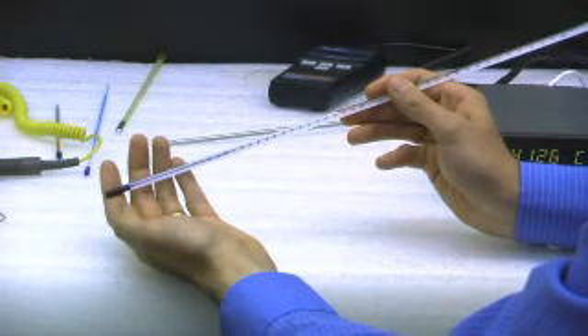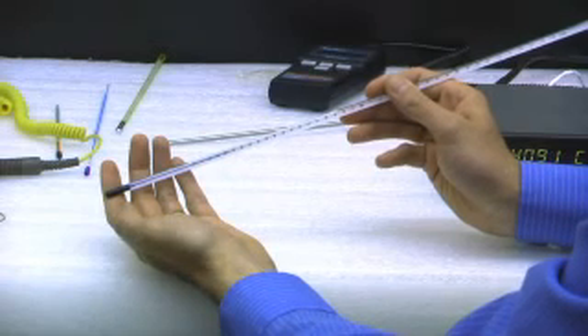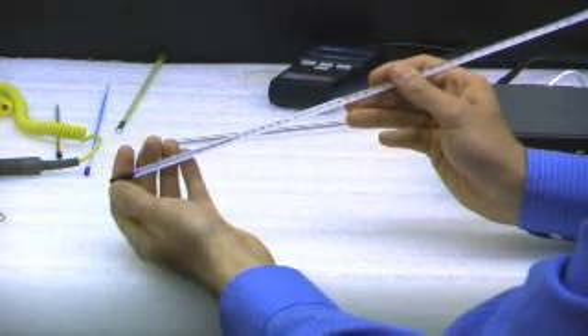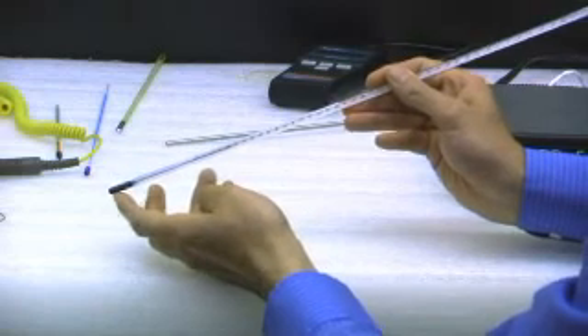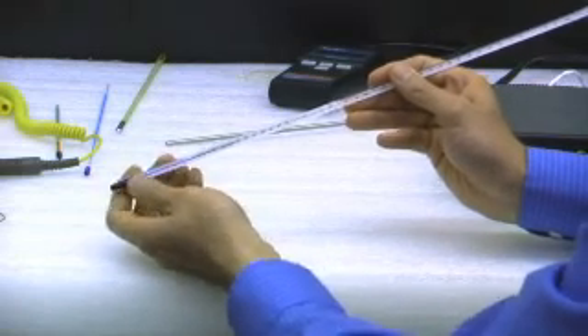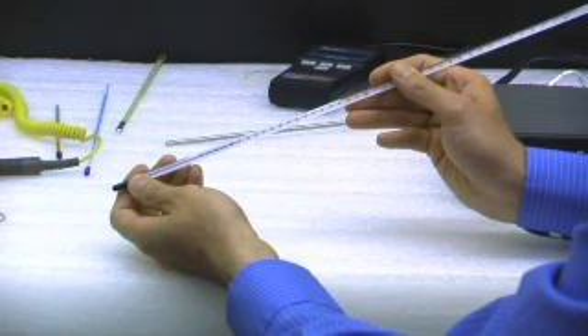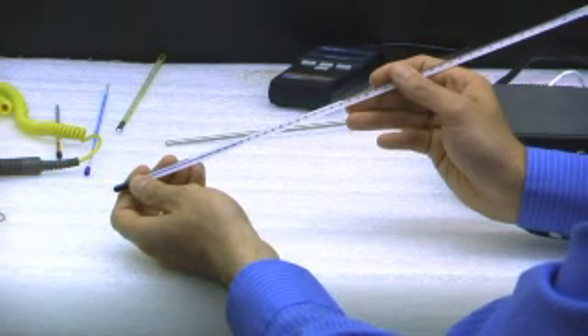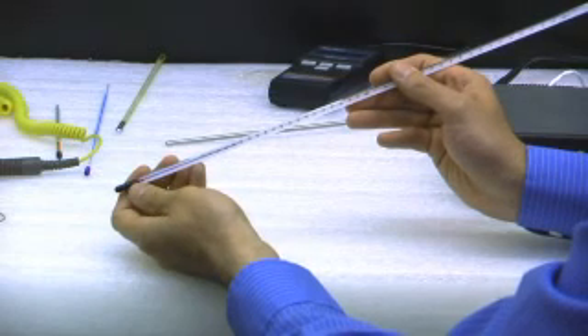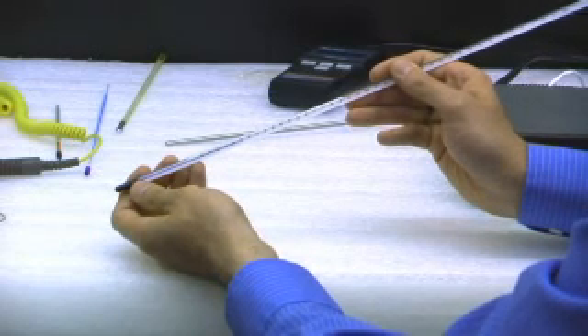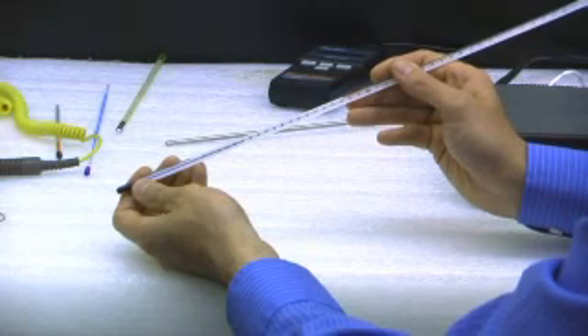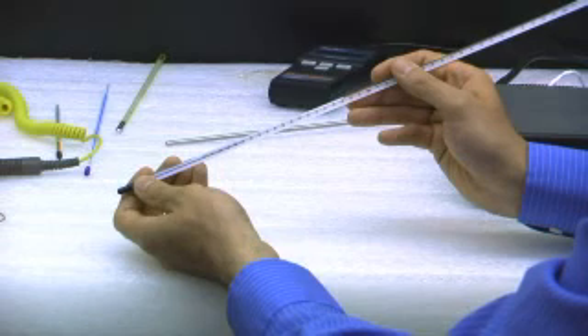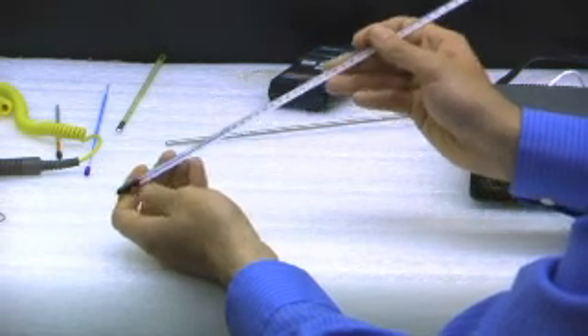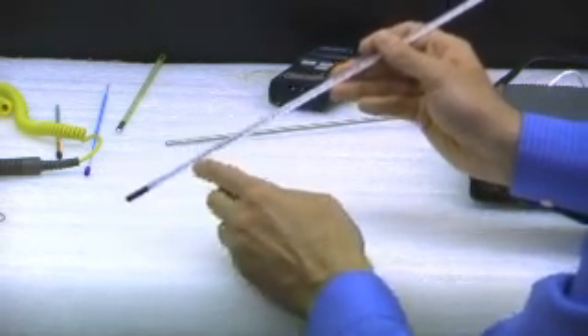Another common substitute for mercury thermometers is another type of glass thermometer. This time the bulb is filled with a non-toxic liquid down at the bottom. Organic liquid-filled thermometers are a good choice if your uncertainty requirements are modest, perhaps 0.5 degrees Celsius or 1 degree Fahrenheit. These are a good choice also if your temperature range is limited, between -100 to +100 degrees Celsius. You do have to watch on shipping about separation of the column.